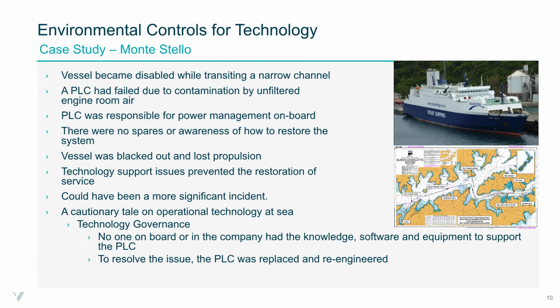So it was playing a critical role in onboard power management. When the PLC failed, all of the generators were dropped off the switchboard, and essentially the ship was blacked out. As a result, the vessel lost propulsion and was essentially disabled, and the crew were forced to anchor. The vessel was in quite a vulnerable position until sometime later, when power was reconnected to the board through a recovery mechanism.